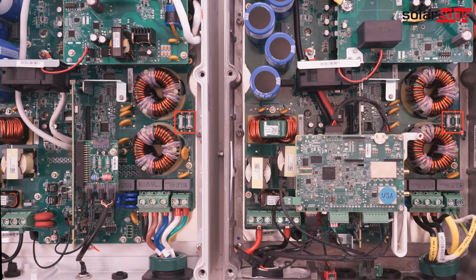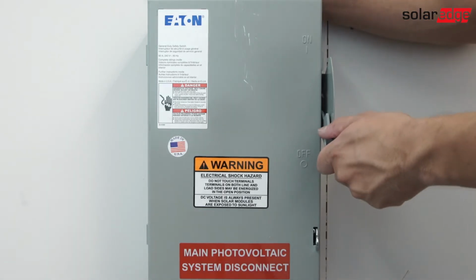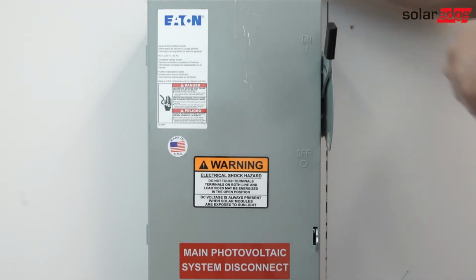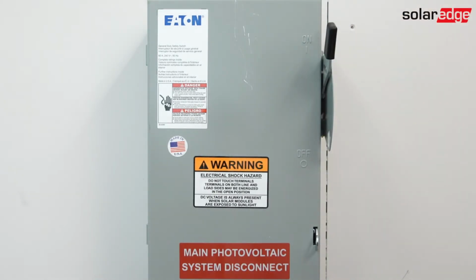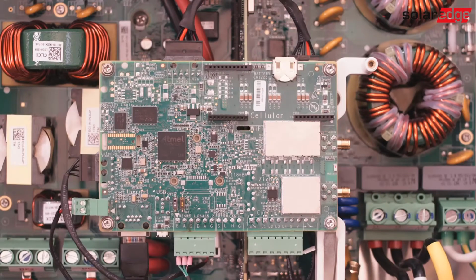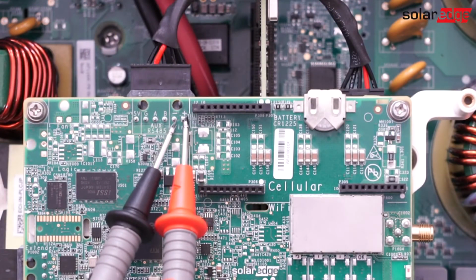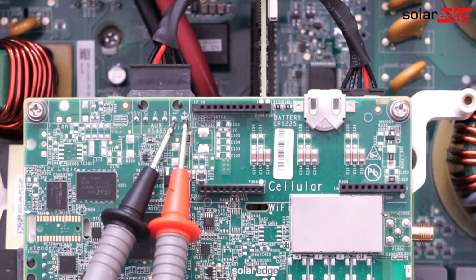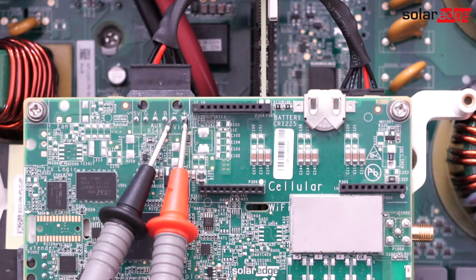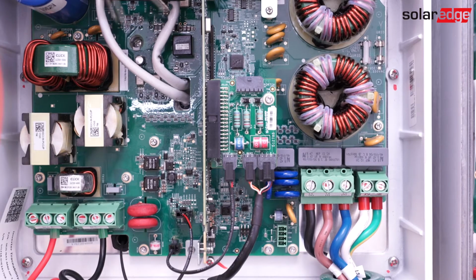After the fuse continuity has been tested, turn the AC power back on to test the VIN voltage on the communication board. The primary unit will have 2 pins at the top of the board next to the cellular connection marked positive and negative and labeled VIN. Place the red probe on the positive and the black probe on the negative and record DC voltage. Expected voltage is between 13 and 18 volts.